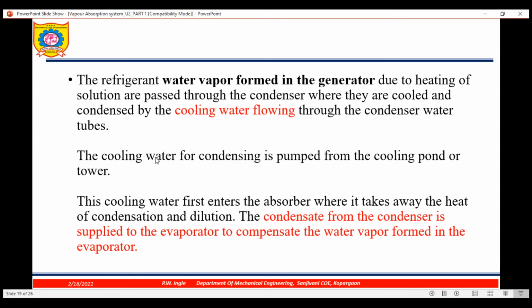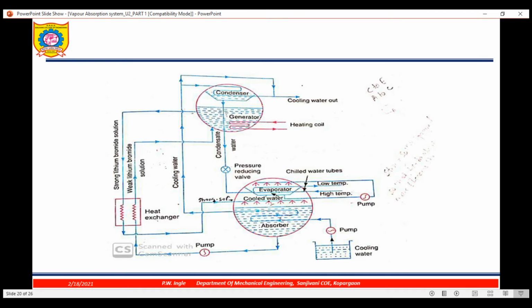The cooling water for the condensing is pumped from the cooling pond or tower. Now cooling water is required for condensation of refrigerant because we are getting refrigerant from where? From the generator. It gets separated out. Refrigerant from the LiBr solution will get separated out. It will be condensed by cooling water. From where is the cooling water coming? You see here. This is the cooling water circuit. Okay.